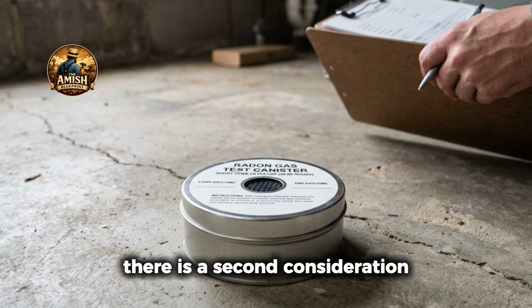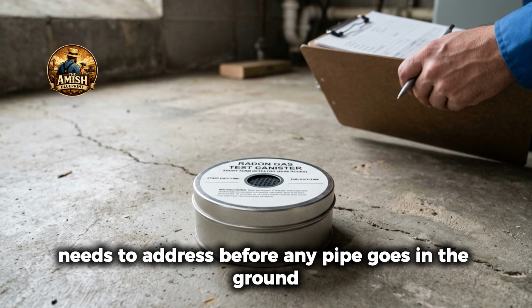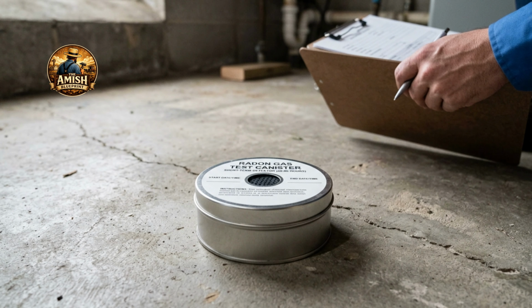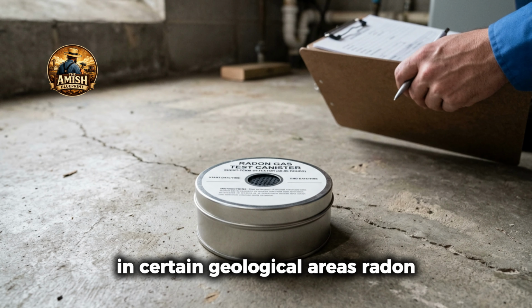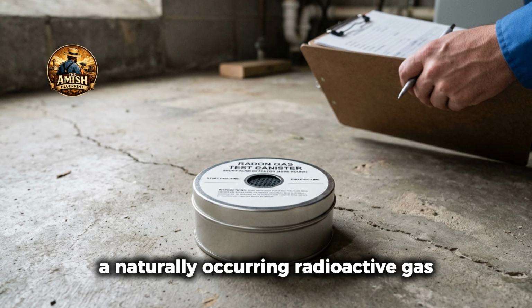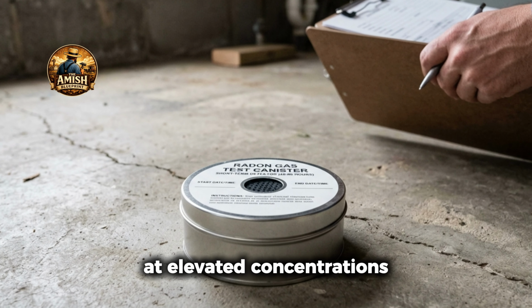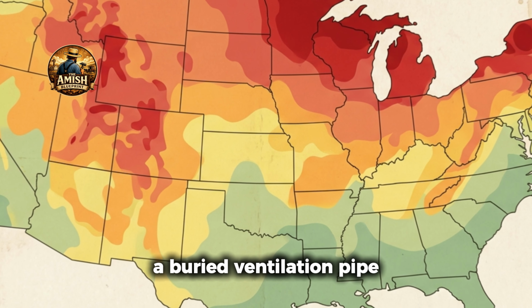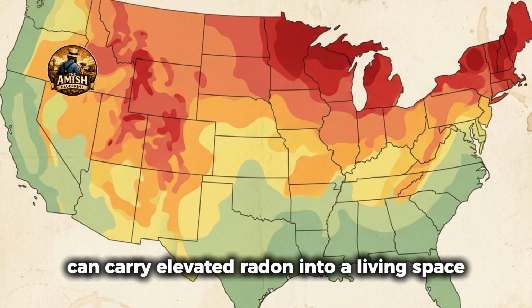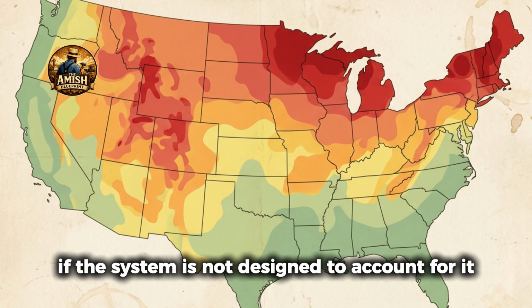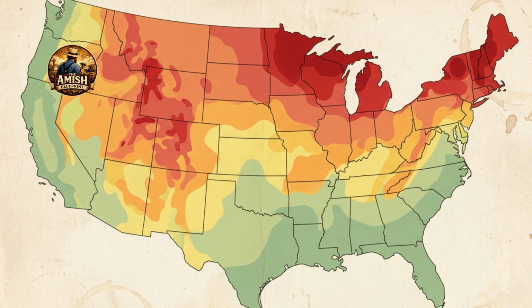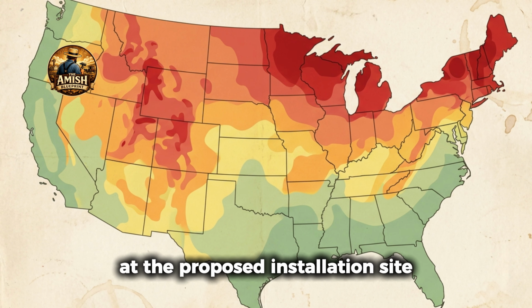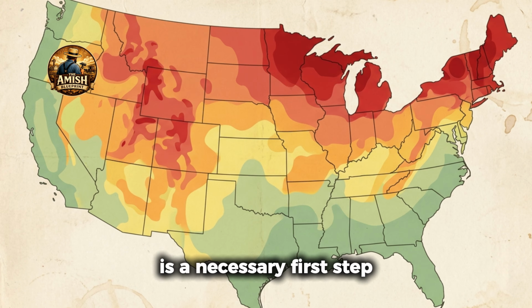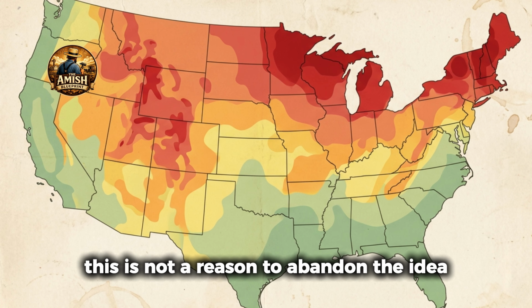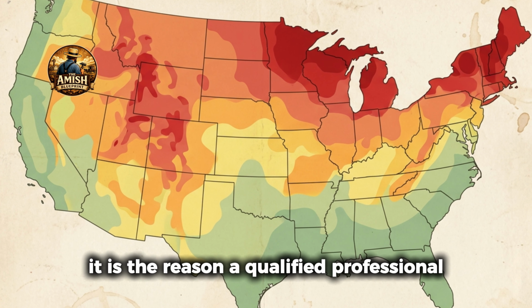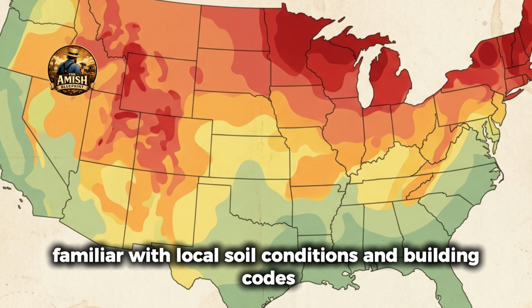There is a second consideration that anyone thinking about an earth tube system needs to address before any pipe goes in the ground. In certain geological areas, radon, a naturally occurring radioactive gas, is present in soil and groundwater at elevated concentrations. A buried ventilation pipe drawing air through those soils can carry elevated radon into a living space if the system is not designed to account for it. A radon test of the soil and air at the proposed installation site is a necessary first step. This is not a reason to abandon the idea. It is the reason a qualified professional familiar with local soil conditions and building codes should be part of any real installation decision.